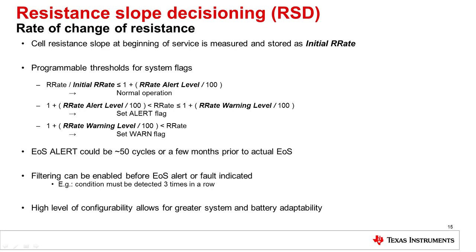Similar to DRD, RSD captures at the very beginning, when the cell is first put into operation, an initial R rate value — how is the cell resistance changing versus time — and stores that in flash memory for comparison. During operation, it captures new values of the R rate and compares each new value as a ratio to the initial R rate, comparing that to various thresholds. If it's below the alert level threshold, no significant aging is assumed. After passing the first threshold, an alert flag is set indicating moderate aging. After passing the second threshold, the warning flag is set indicating the cell most likely needs replacement. Just like DRD, there is also filtering so you can require multiple readings above the threshold before alerts are actually triggered.